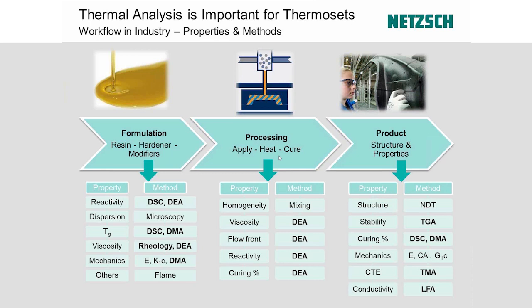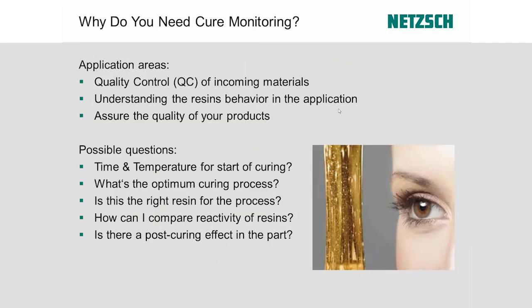Classical lab-scale characterization technologies cannot be applied during processing — except DEA. DEA has its strength both in the lab, characterizing neat resins, and in processing, where specific sensors monitor viscosity, flow front, infusion processes, reactivity, and degree of curing. On the final cured part, DEA is less strong, though it can characterize glass transition; DSC, DMA, and laser flash analysis are more suitable there.